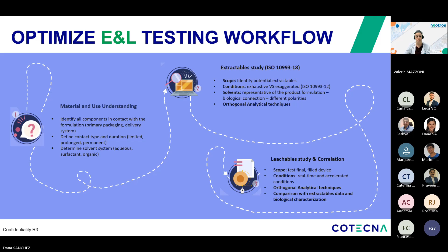But when designing extractable and leachable studies, one of our most important responsibilities is to use stressed extraction conditions that challenge the system, yet do not alter the fundamental state of the formulation or of the material. Stress conditions such as elevated temperature, extended contact time, or aggressive solvents are essential to reveal the chemical species a device could release under worst-case scenarios. But if those conditions degrade the formulation or damage the material in ways that would never occur during real use, the study no longer reflects true patient risk.